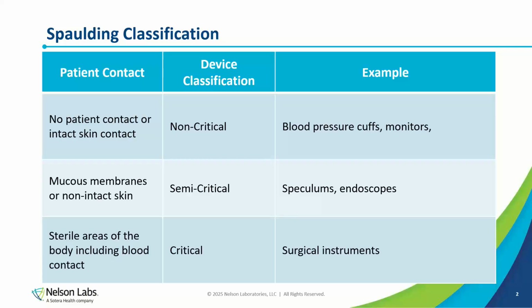And it's the one that most hospitals are going to have access to, that is moist heat or steam sterilization. But as we all know, not every material and not all devices can withstand such high temperatures and pressures, and so you may want to look at alternative methods such as vaporized hydrogen peroxide or ethylene oxide. Those again have their own limitations with material and electronic equipment as well. So when you're choosing your sterilization method, you really are going to have to take into account the design of your device, the materials of your device, and the mechanics of the device as well, because you want to make sure that the device after sterilization can still function properly. But that is an excellent question as well.